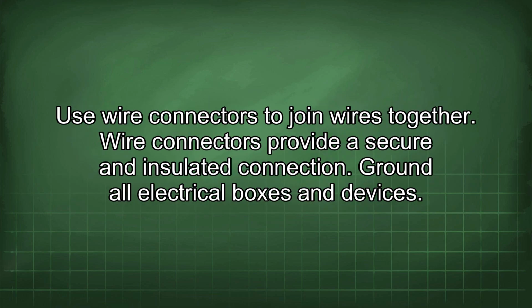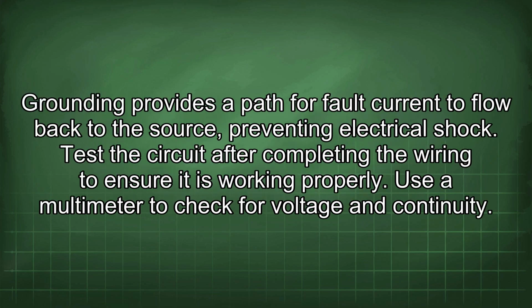Use wire connectors to join wires together. Wire connectors provide a secure and insulated connection. Ground all electrical boxes and devices. Grounding provides a path for fault current to flow back to the source, preventing electrical shock. Test the circuit after completing the wiring to ensure it is working properly. Use a multimeter to check for voltage and continuity.